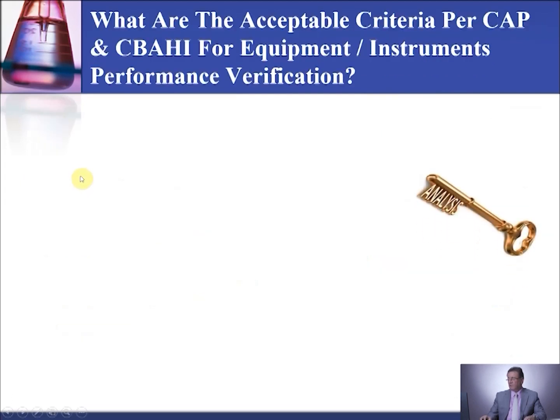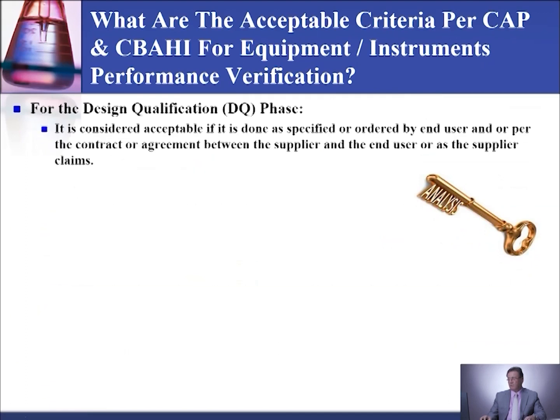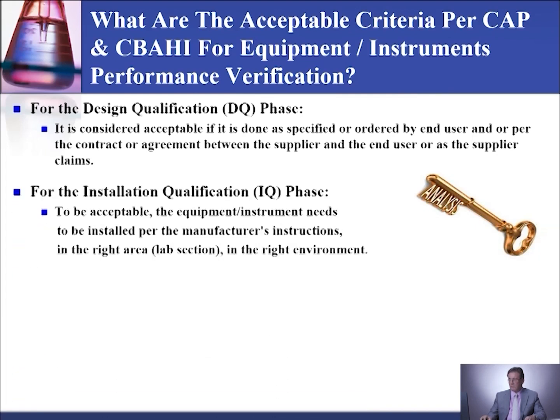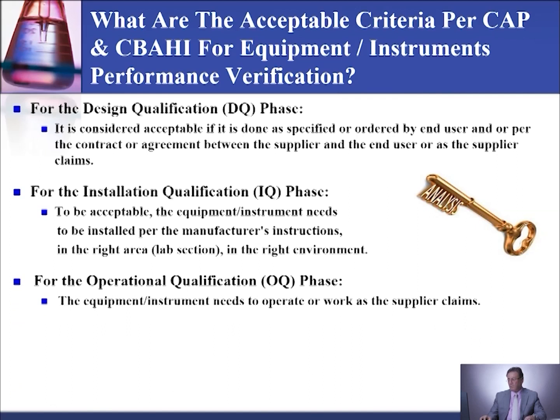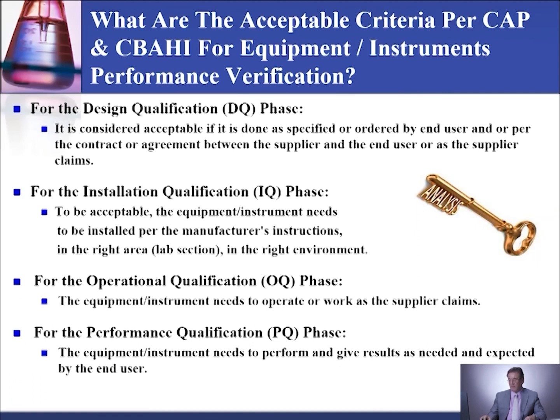What are the acceptance criteria per CAP and CBAHI for equipment and instrument performance verification? For the design qualification phase, it is considered acceptable if it is done as specified or ordered by the end user, the laboratory, and/or per the contract or agreement between the supplier and the end user, or as the supplier claims. For the installation qualification phase, it is acceptable if the equipment or instrument is installed per the manufacturer instructions in the right area and the right environment. For the operational qualification phase, the equipment or instrument needs to operate as the supplier claimed. For the performance qualification phase, the equipment or instrument needs to perform and give results as needed and expected by the end user.